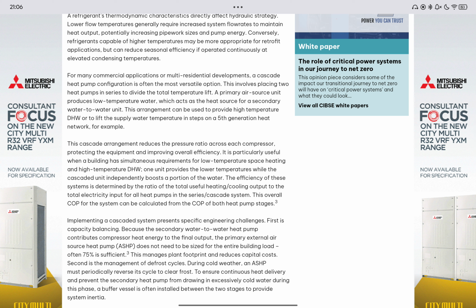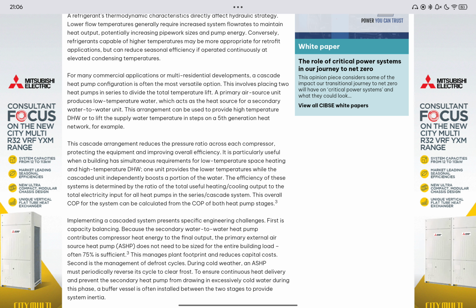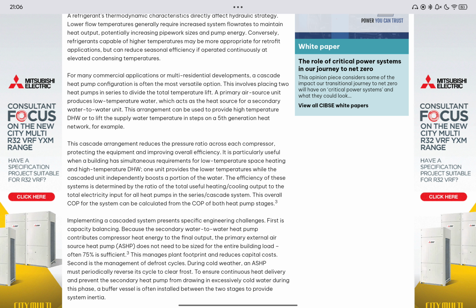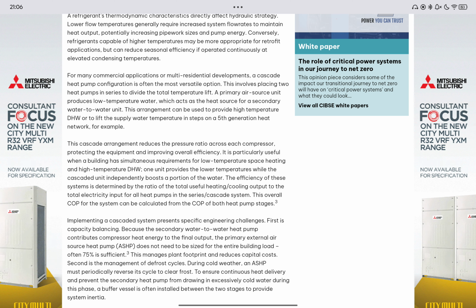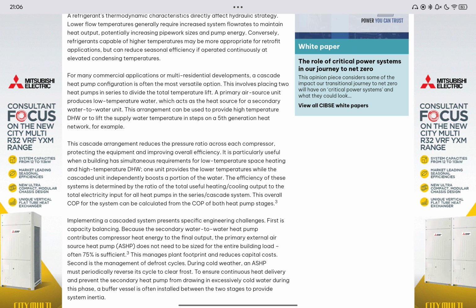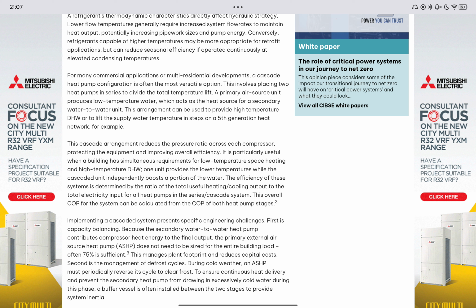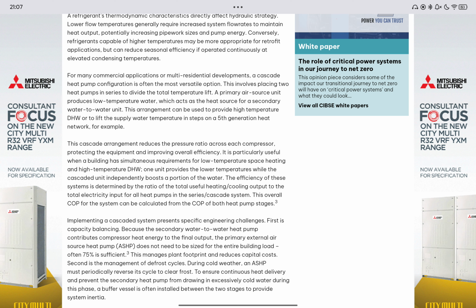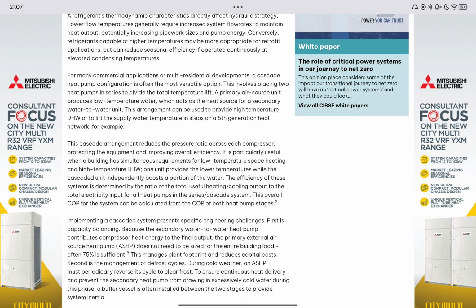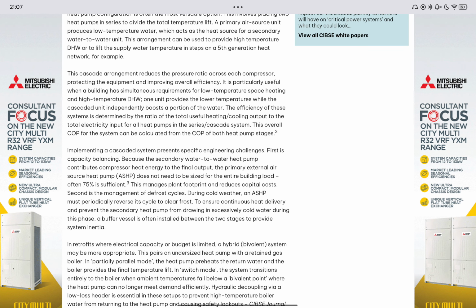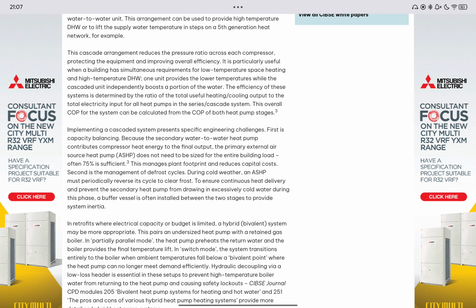For many commercial applications or multi-residential developments, a cascade heat pump configuration is often the most versatile option. This involves placing two heat pumps in series to divide the total temperature lift. A primary air source unit produces low temperature water, which acts as the heat source for a secondary water-to-water unit. This arrangement can be used to provide high temperature DHW or to lift the supply water temperature in steps on a fifth generation heat network, for example. This cascade arrangement reduces the pressure ratio across each compressor, protecting the equipment and improving overall efficiency.